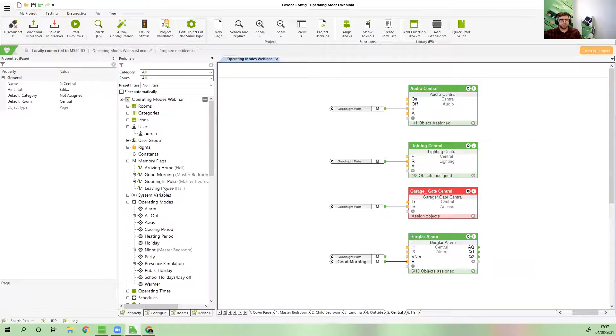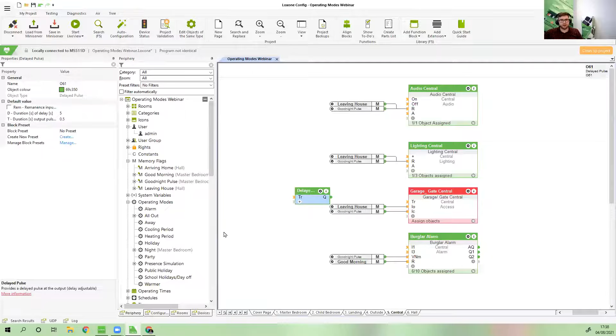And I could say that I want to go to the away operating mode for a period of time that starts on the 2nd of September and ends on the 7th of September, which is when I'm going on holiday. And then automatically between those dates, it will be in the away operating mode. So that's then another way that you can do operating modes.